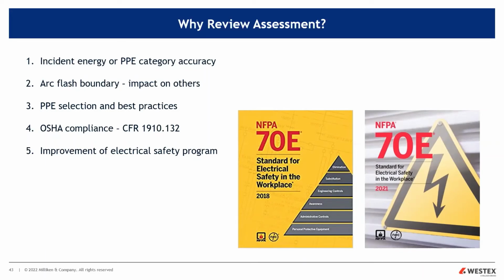A lot of times the person that's watching the person doing the work thinks they're outside the boundary. They're not in PPE. Well, if that boundary has changed because you changed the equipment or the circuit breaker and the cycle time is longer, that may change. Again, for PPE selection, make sure the arc rating's right. Maybe we need to go to a daily wear program, or maybe all this stuff has really reduced our incident energies, hardly any exposure. Maybe we can go to a task-based program.